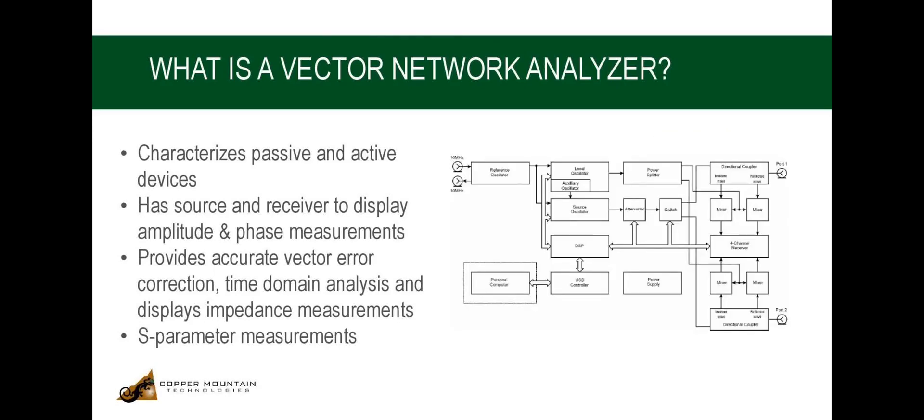Now, let us see how a two-port USB VNA works internally. The analyzer consists of a source oscillator, a local oscillator, source power attenuator, and a switch connecting the source signal to two directional couplers which are connected to port 1 and port 2 of the VNA.